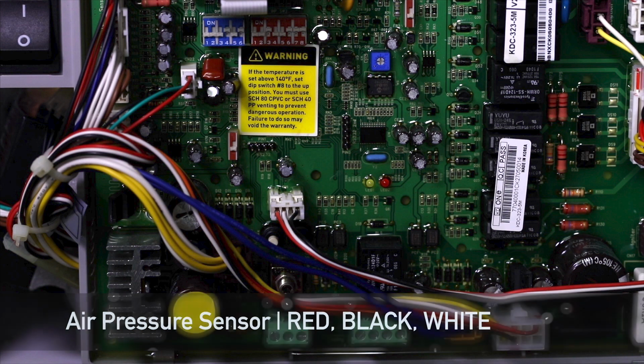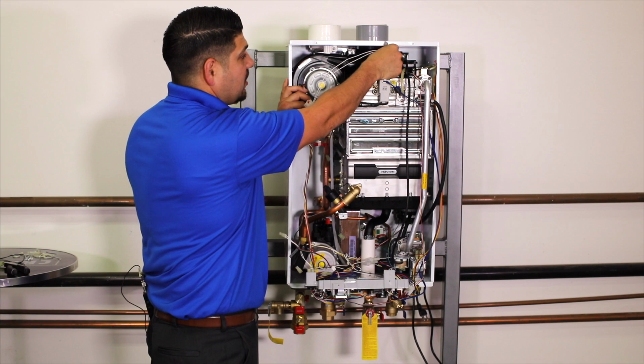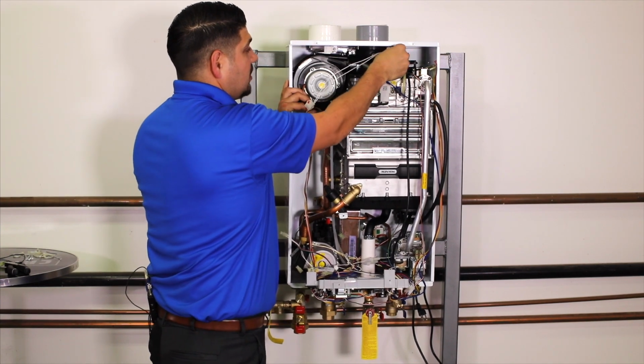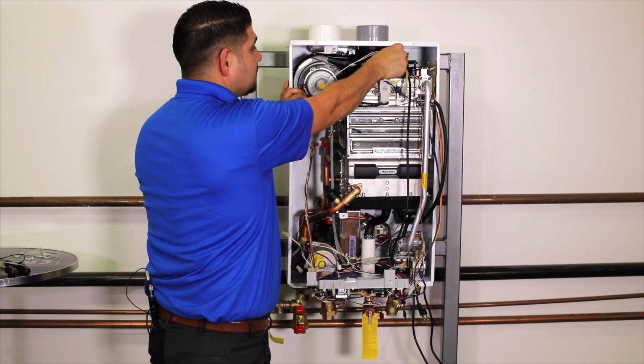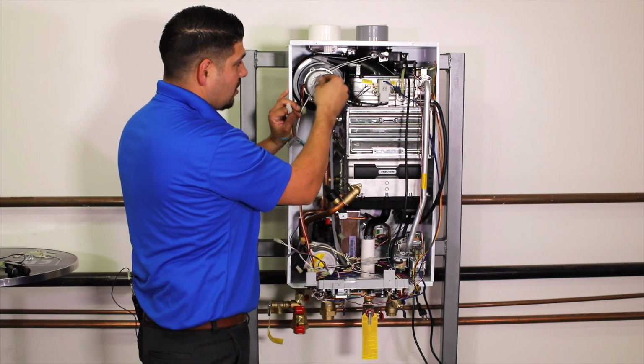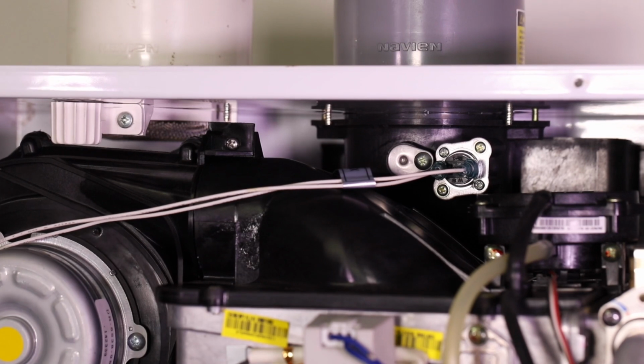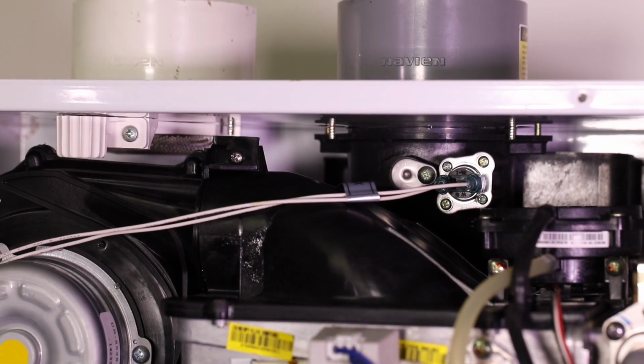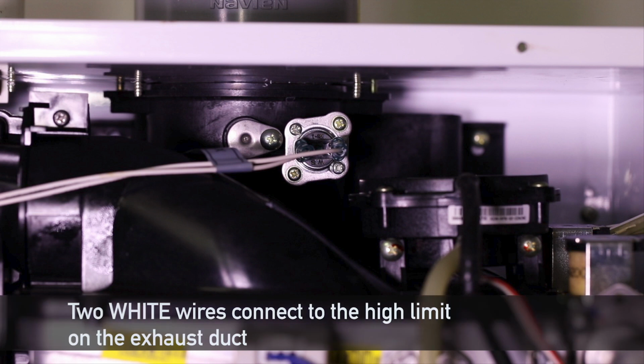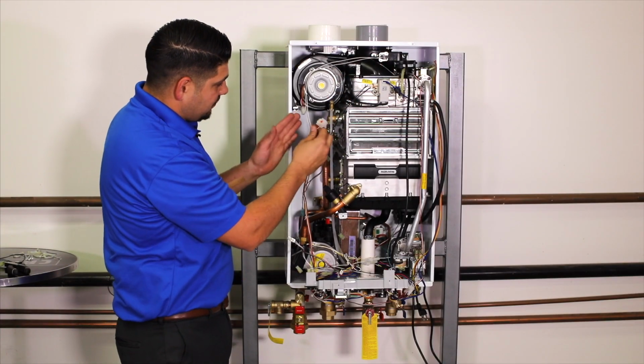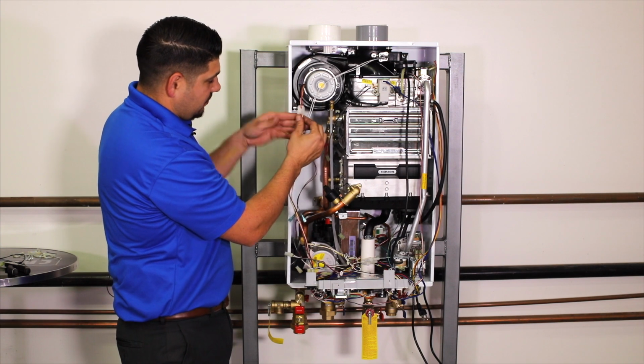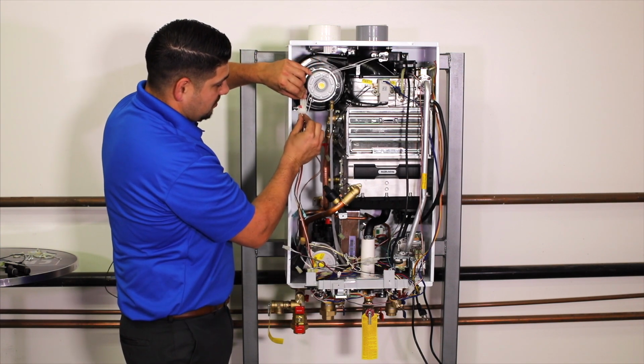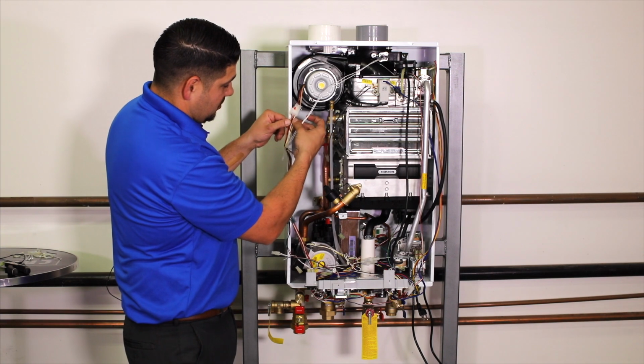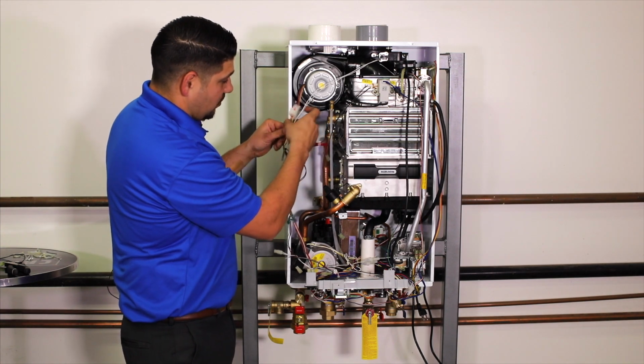Now we're going to go to the wiring on the other side of the unit. We're going to start our way up on the top here, and on our exhaust duct, these two white wires, these longest ones you have, we're going to fish around there, but they're going to connect to your high limit right here on your exhaust duct. Following down those two white wires, you got this big connector, and this here is going to connect to your fan. This is your yellow, white, orange, black, and red wire.